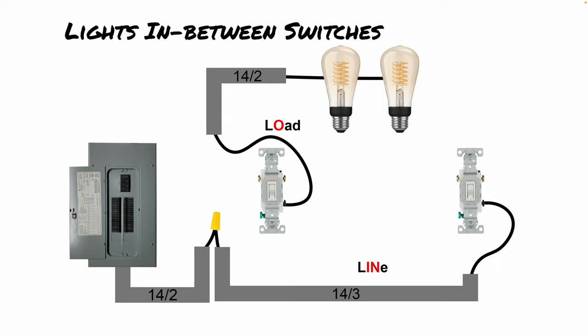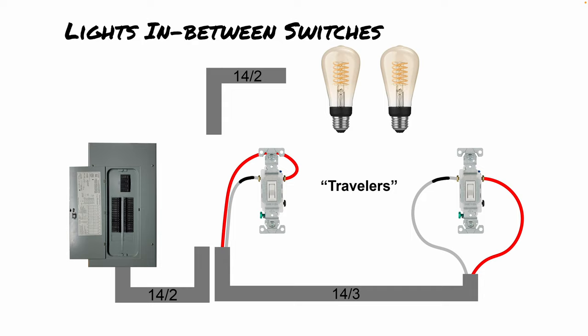First, let's talk about line versus load again. The line comes in from the electrical panel and goes all the way over to the last switch, connected to the black terminal. On the second switch — the one with the lights wired to it — the black terminal connects up to the light fixtures. That's the line versus load situation here. For the travelers, we're using a red wire plus a white wire marked with black tape, because the black wire is being used to carry power all the way to the last switch.